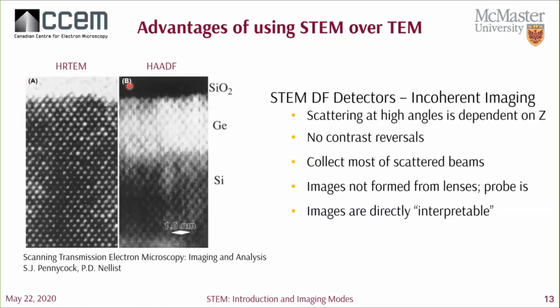So from the cross correlation, we can also deduce that our image resolution is dependent on the probe size. So a finer probe would allow us to collect scattering from a single atom, giving us images similar to that shown here, in which we can see the adsorption of atomic platinum on titanium dioxide. And lastly, since our images are not formed by objective and projection lenses, the images themselves don't suffer from aberrations produced from the lenses.